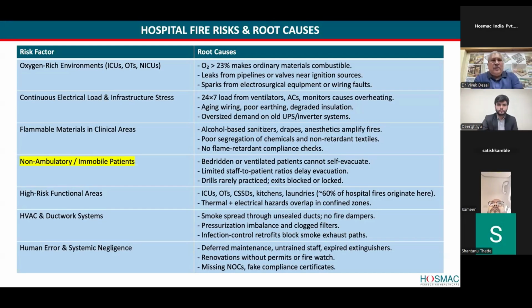Then the third is flammable material in clinical areas. Because post-COVID, all of you have used sanitizers which are alcohol based. There are drapes, curtains, consumables, which are one-use kinds of consumables. Anesthetics amplify fire because anesthesia gases are inflammable. There is poor segregation of chemicals and non-retardant textiles. So you should have a storage system which very clearly defines these kinds of inflammable materials, to be segregated from non-inflammable materials, and they should be under lock and key as far as possible, so that they are not exposed. No flame retardant compliance checks we do, actually, to be honest. You can check yourself. If you are from a hospital and registered, then you will yourself see that you haven't done this probably ever.